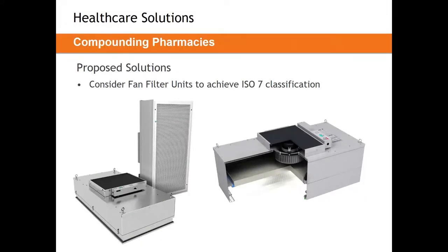Where rooftop equipment can't provide the pressure drop needed for ISO Class 7 HEPA filtration, fan filter units are a good solution to provide that boost. A newer product is a fan filter unit with integrated high-quality LED lighting — useful because compounding pharmacies are small spaces with limited ceiling area, and combining the HEPA filter diffuser and lighting into one unit can greatly benefit the ceiling layout.